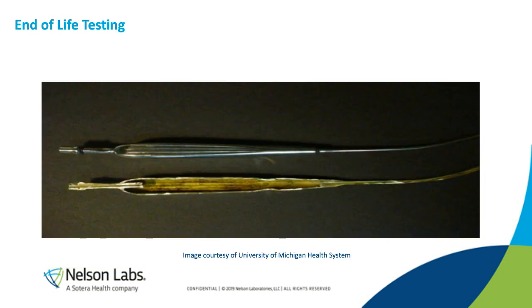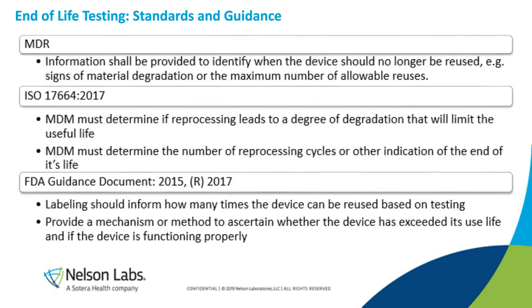Now, one thing I wanted to touch on briefly as well is end-of-use testing. So this shows when a device is at the end of its life. There is specific information in the medical device regulation and also in the ISO 17664 and the FDA guidance document that was republished in 2017. The MDR states that information shall be provided to identify when the device should no longer be reused. For example, it would show signs of material degradation or the maximum number of allowable reuses.